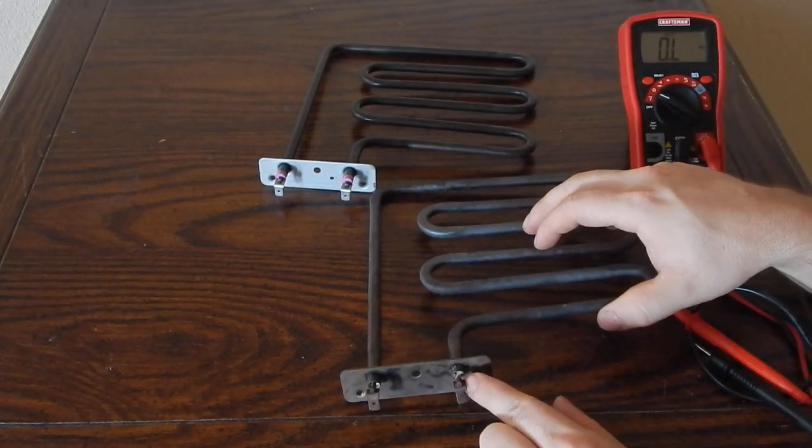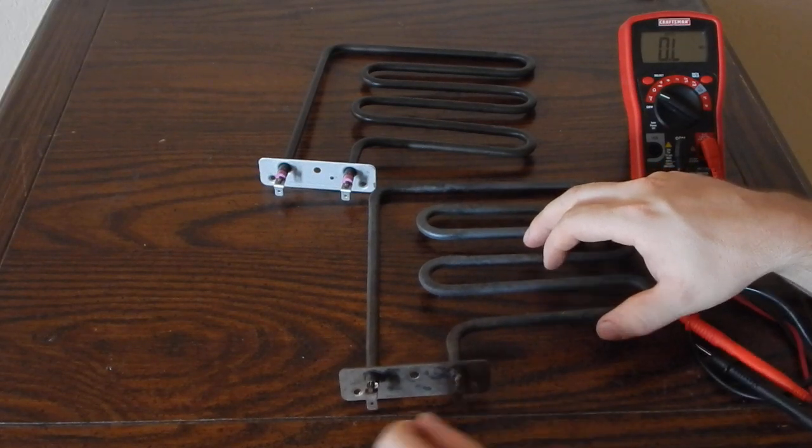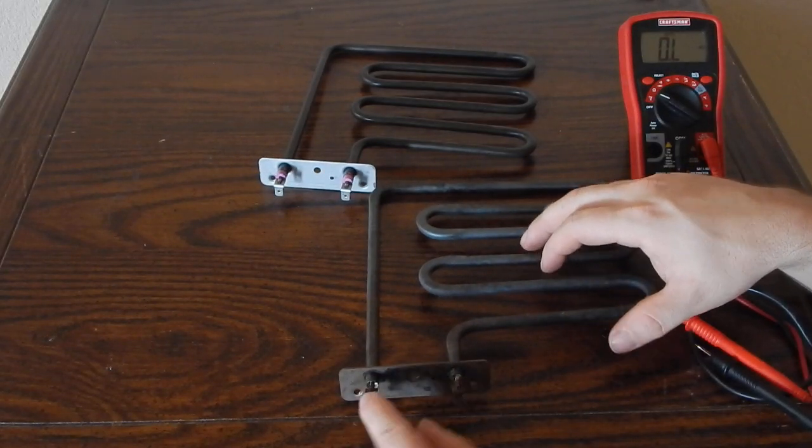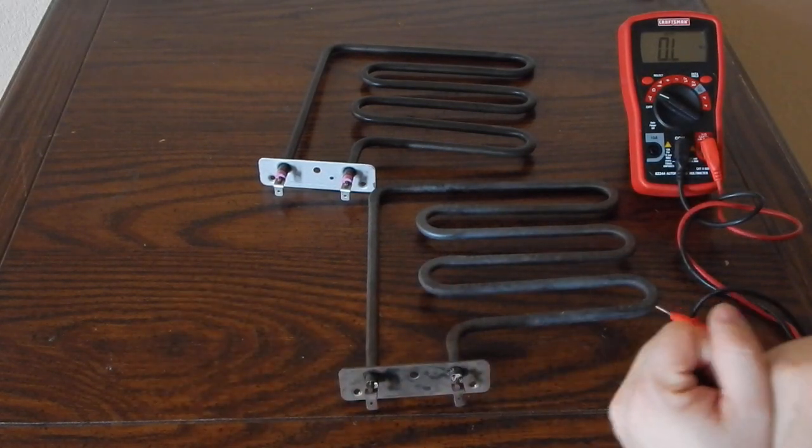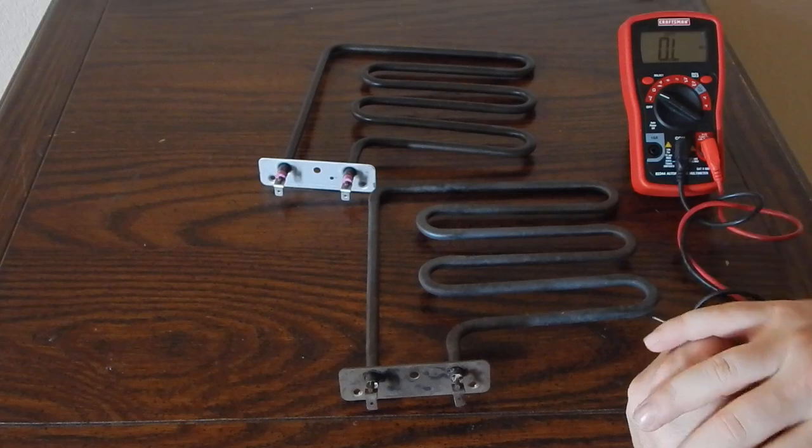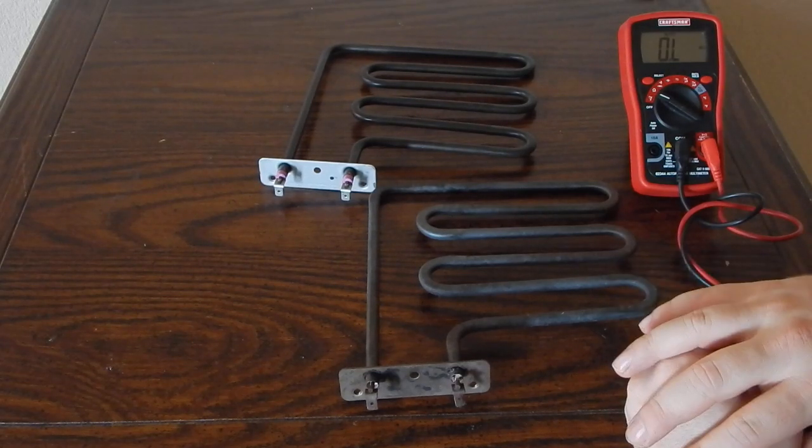If that ceramic breaks down, then you could potentially have a connection between the internal wire and the outside casing, which is obviously bad. That's what happened here and the GFI breaker caught it and shut it off.